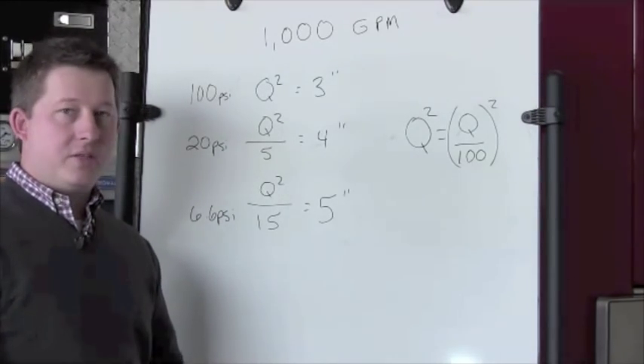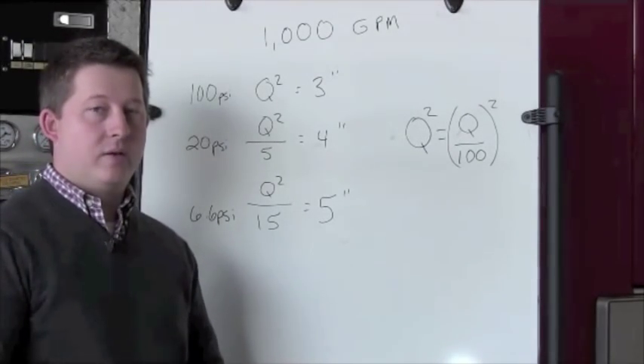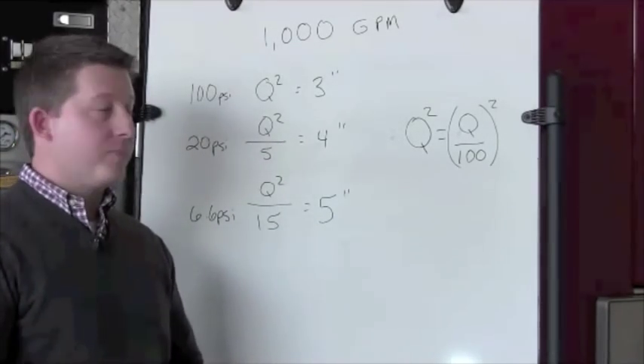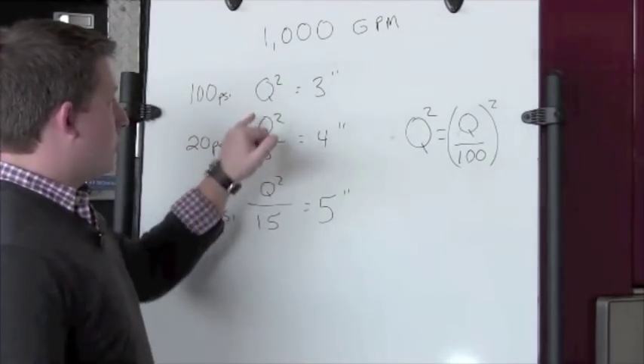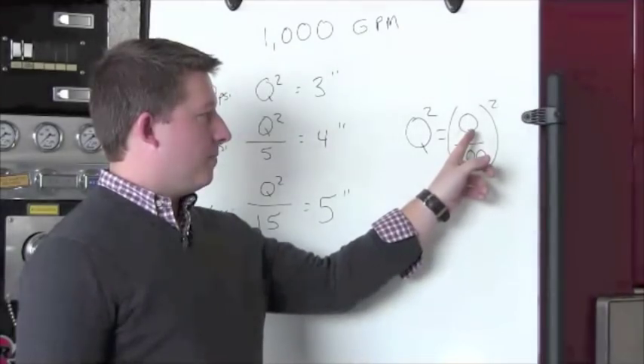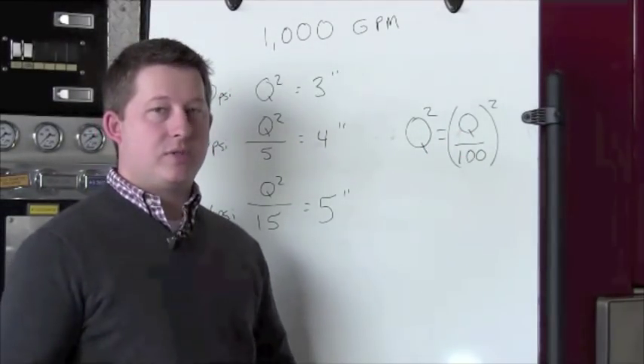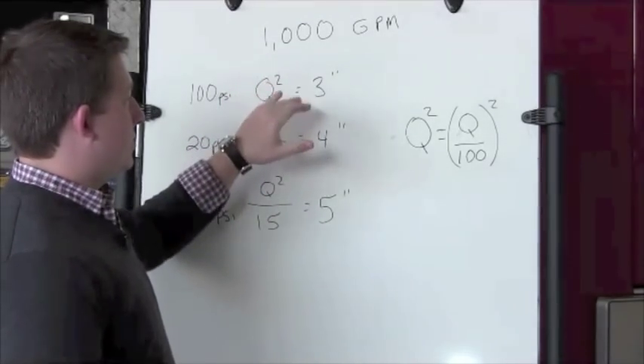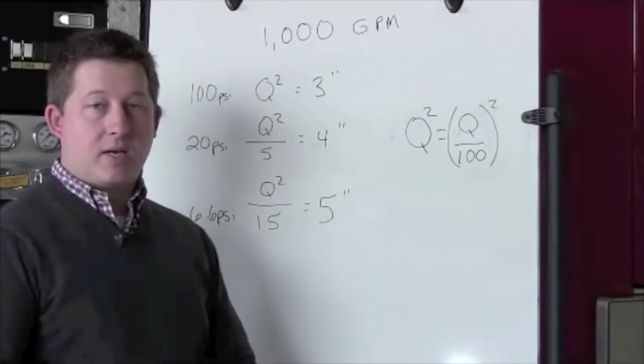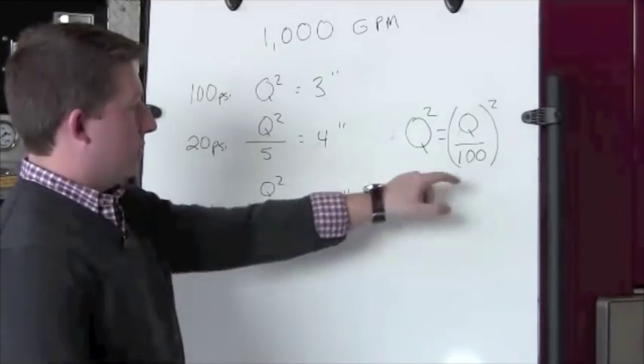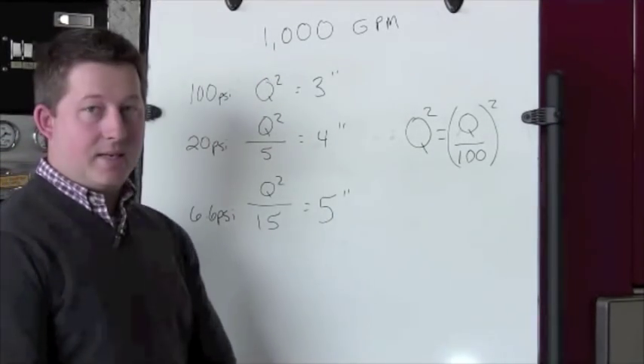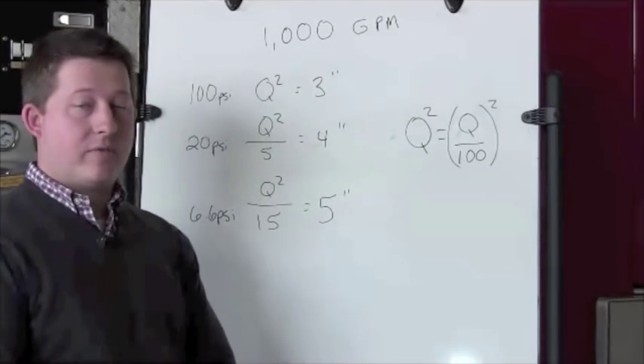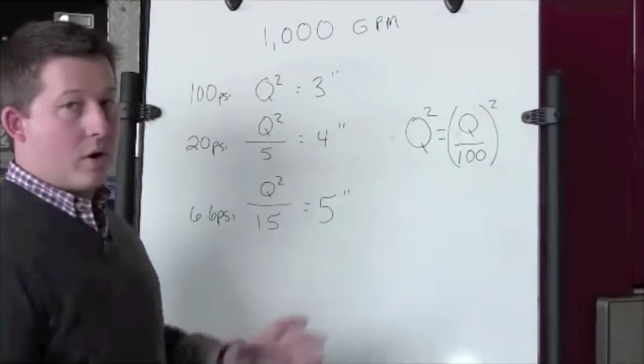This is something pretty easy to do on the fire ground in your head — the condensed Q method. We generally use this for three inch, four inch, and five inch supply lines. Q squared is the quantity of water divided by 100, squared — so it's in hundreds of gallons per minute. For example, if we're flowing 1,000 GPM through a three inch line, Q is 1,000 divided by 100, which is 10. Ten squared equals 100, so we have 100 psi friction loss per 100 feet in a three inch line.